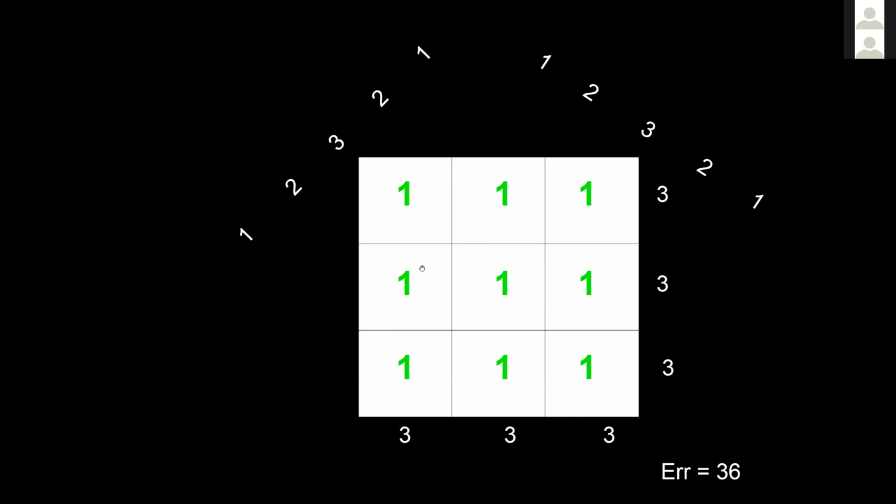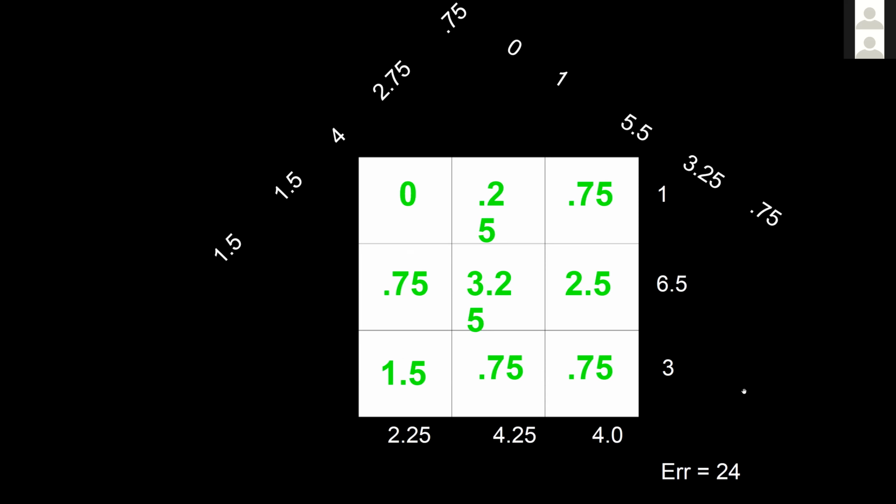Then you calculate what the projection is at each angle. Then you compare with this. Once you have this, you look at what the projection should be in your detector, and you compare it with what you measured. Then you get an error. You backpropagate the error into each voxel, adjust that.